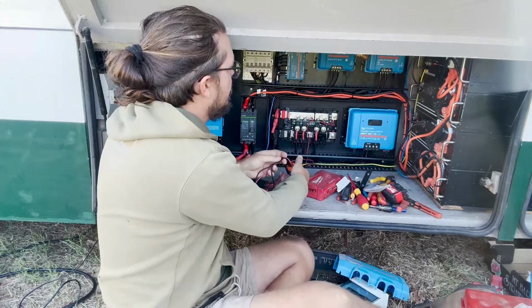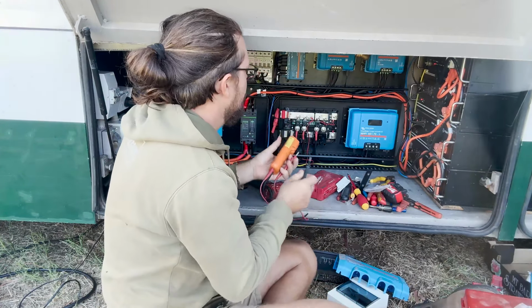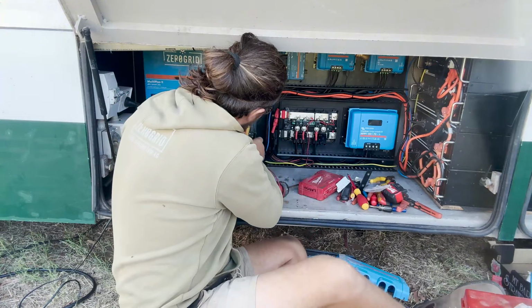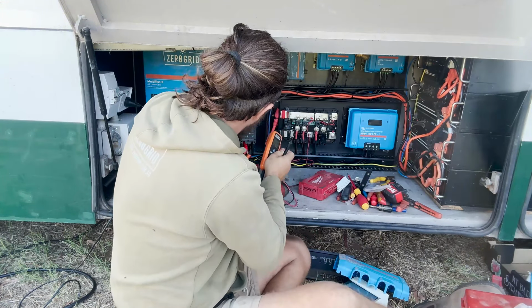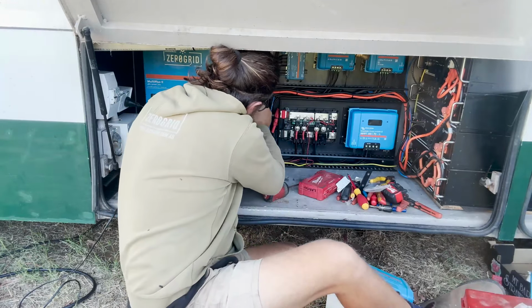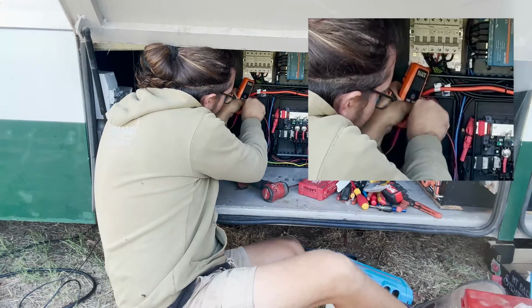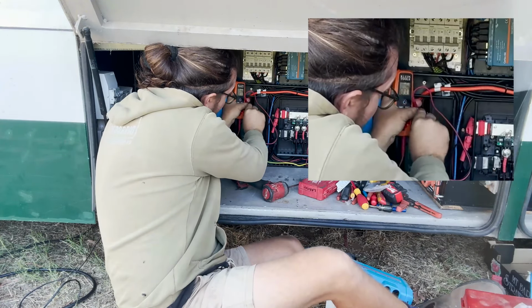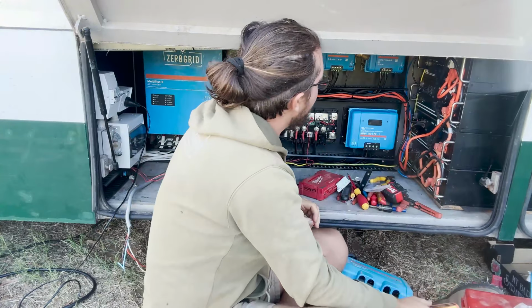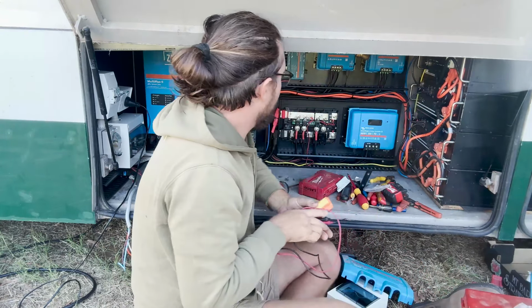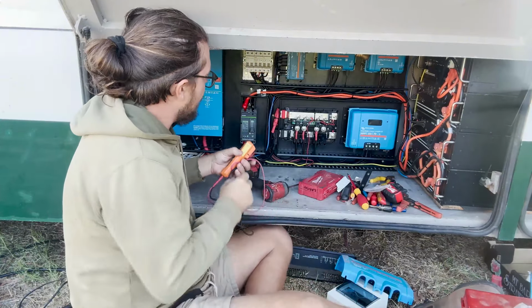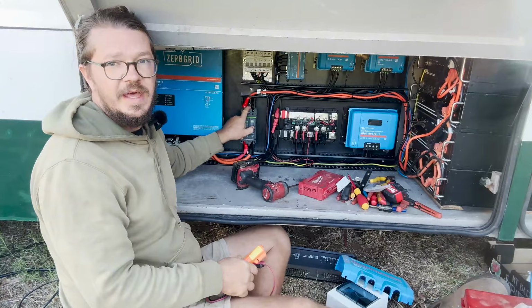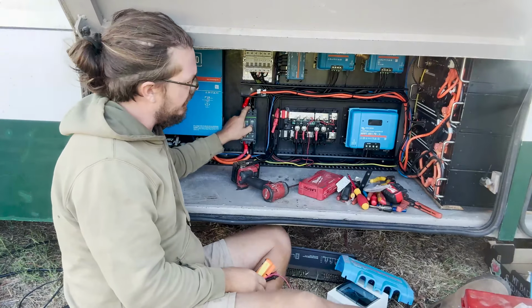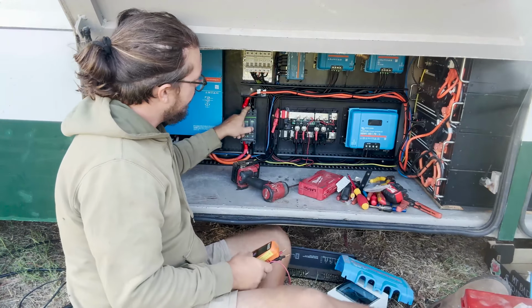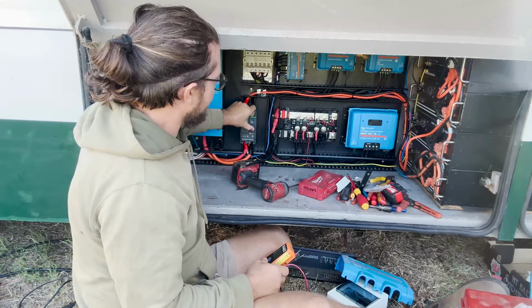They're just a bit slow, but then we should get a battery voltage at the top of this isolator. It's a little hard to see, and this is where it's painful showing on video, but we can check for voltage on the top of that isolator to make sure we're getting some battery bank voltage there, then go ahead and turn that one on.